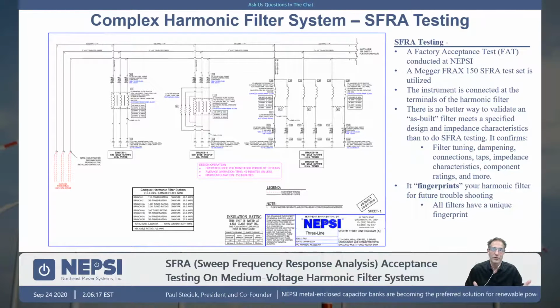So today we are talking about sweep frequency response analysis. It's a test method that NEPSI started approximately 2 years ago. It's a factory acceptance test that we do on all of our harmonic filters. And essentially what it does is it helps to guarantee that the tuning point and the damping factor and other various aspects of that harmonic filter meet the specification.